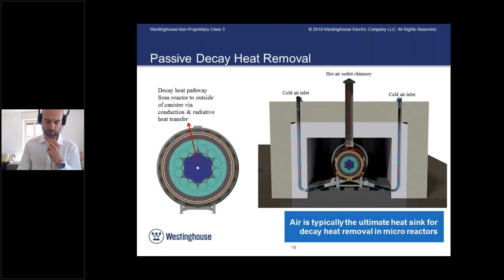Decay heat removal is most often done by exchanging heat ultimately to air — air is the ultimate heat sink. Many microreactor designs — you can see the example from eVinci — have a chimney where hot air can go out from the canister, and there are inlet ports for cold air to come through. There is natural circulation of air inside and around the reactor canister, which guarantees that decay heat can be removed. Air is the ultimate heat sink, broadly abundant and usable in every location.